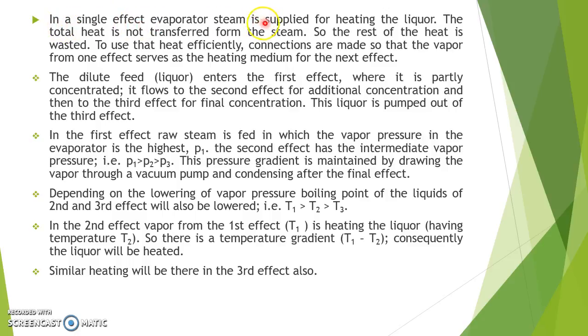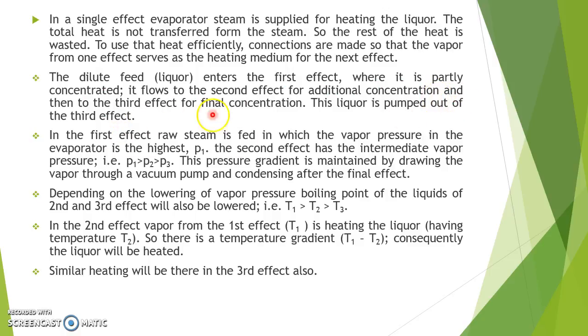In a single effect evaporator, steam is supplied for heating the liquor. The total heat is not transferred from the steam, so the rest of the heat is wasted. To use that heat efficiently, connections are made so that the vapor from one effect serves as the heating medium for the next effect. The dilute feed enters the first effect where it is partly concentrated, then flows to the second effect for additional concentration, and then to the third effect for final concentration. The liquor is pumped out of the third effect.